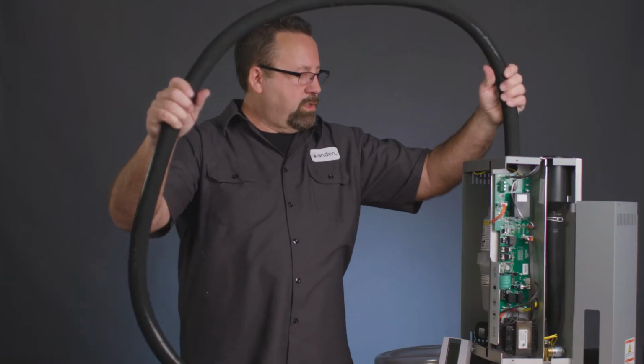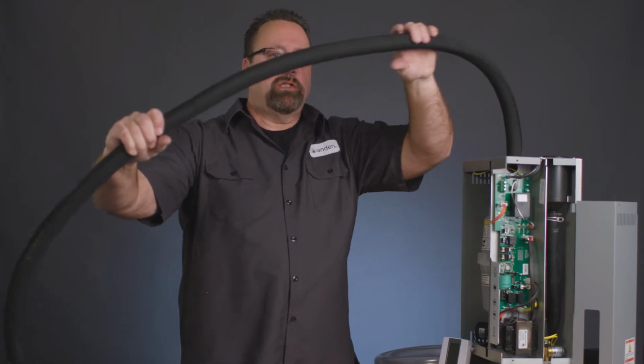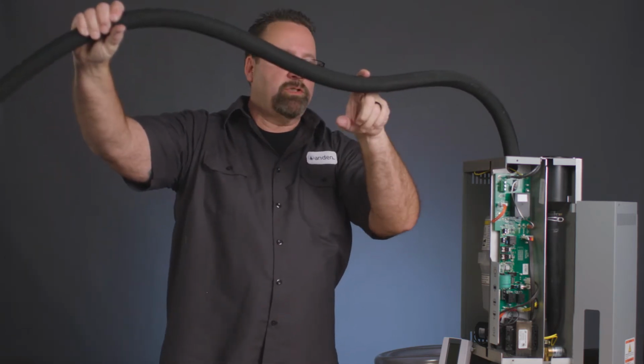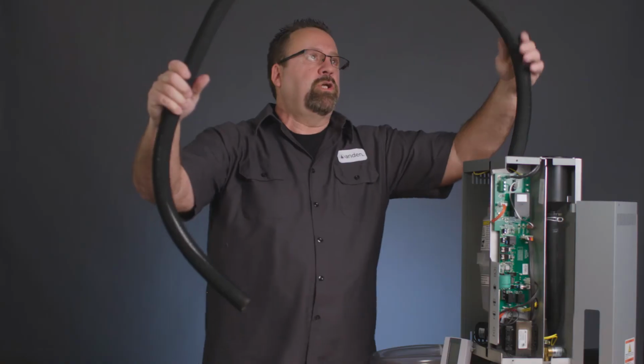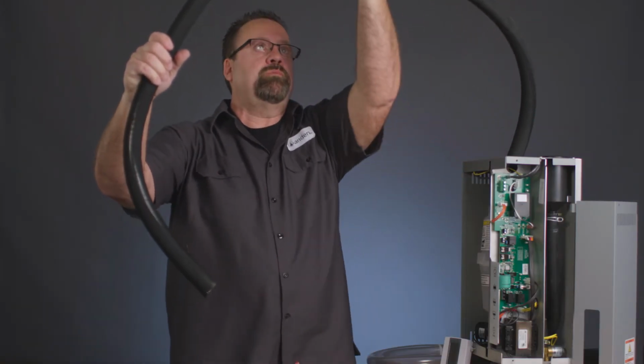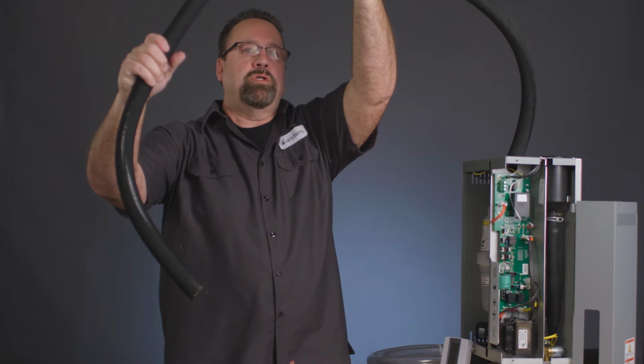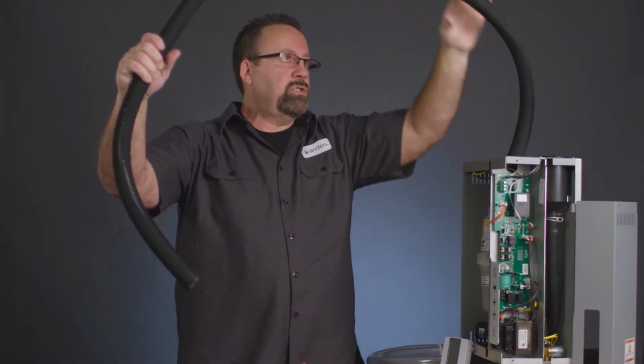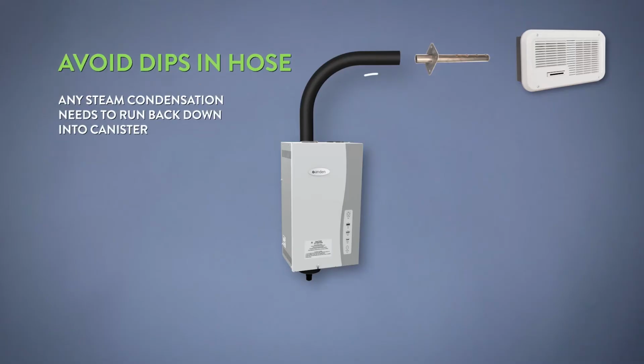When installing this, one of the common mistakes people make is to have a dip somewhere in there, a flat spot where steam can collect, condensation water will collect. That's a big no-no. We want to make sure that this hose goes a nice pitch right to the fan pack or the steam dispersion tube so any condensation forming inside the hose can run back into the canister.